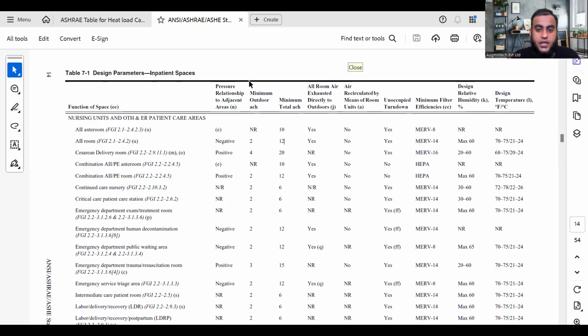Okay, Sujit is telling what is negative pressure, what is positive pressure. So that we'll discuss in detail in our live class, okay? Here, everything is not possible. Even see, here design relative humidity is also given. Maximum how much humidity you can maintain. Relative humidity in isolation room, 60%. And design temperature in Fahrenheit is given between 70 to 75 degrees Fahrenheit.